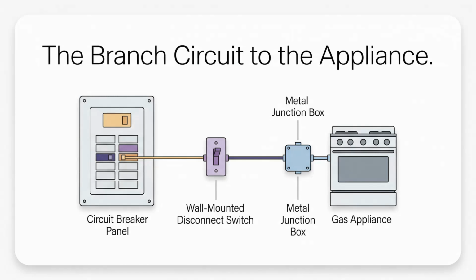Before we look at the appliance itself, we need to understand how power gets there. The branch circuit usually provides 110 volts and consists of three main parts: the circuit breaker at the panel, an appliance disconnect switch located near the unit for safety, and the junction box on the appliance where the final connections are made. At the start of that branch circuit is the circuit breaker.